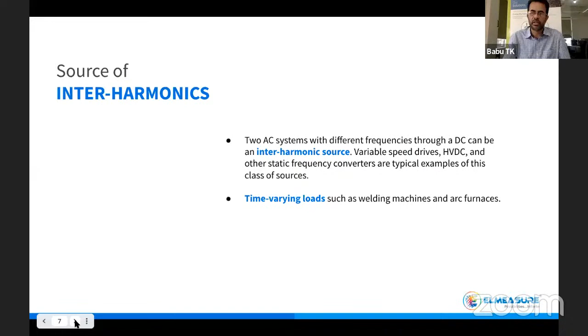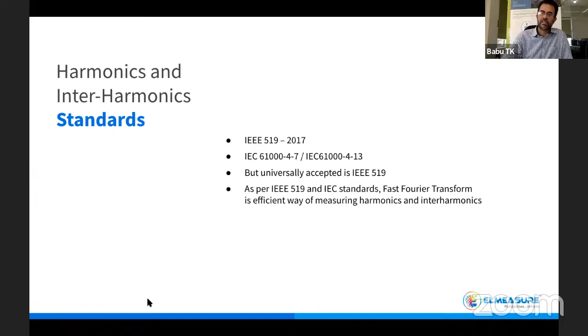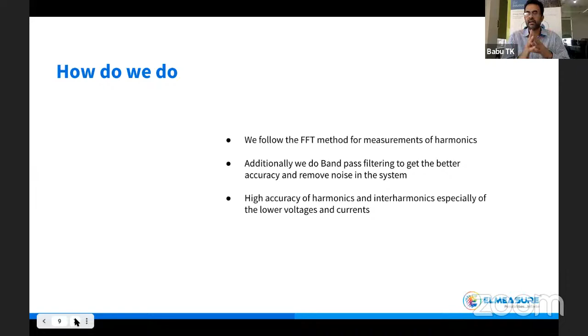The standards: the main one I would say is IEEE 519, and we also use IEC 61000, 4-7 and 4-13, etc. IEEE 519 talks about the fast Fourier transform as an efficient way of measuring harmonics and interharmonics, and we use the same fast Fourier transform mechanism. We do have bandpass filtering to get better accuracy and remove noise from the system. Fortunately, we are able to get reasonably good accuracy even at lower voltage and current levels.